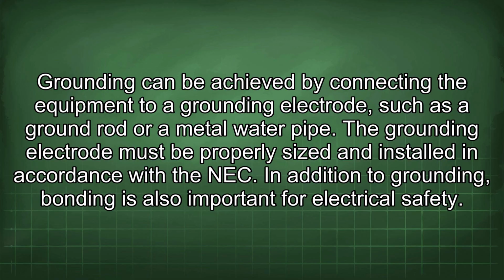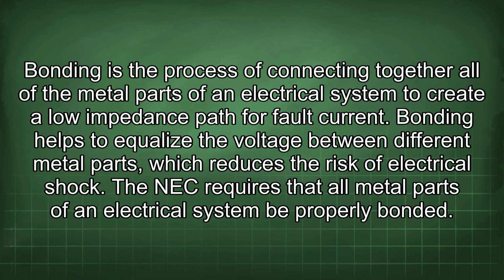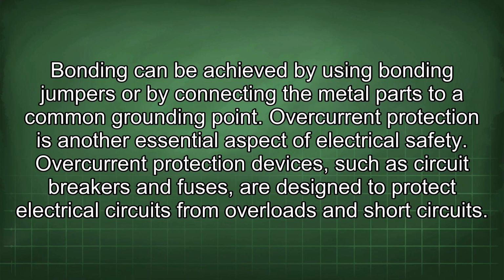In addition to grounding, bonding is also important for electrical safety. Bonding is the process of connecting together all of the metal parts of an electrical system to create a low impedance path for fault current. Bonding helps to equalize the voltage between different metal parts, which reduces the risk of electrical shock. The NEC requires that all metal parts of an electrical system be properly bonded. Bonding can be achieved by using bonding jumpers or by connecting the metal parts to a common grounding point.